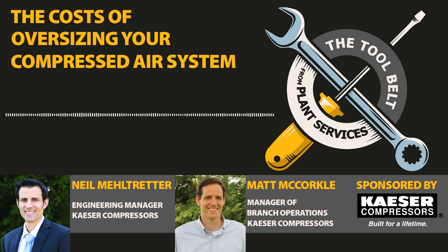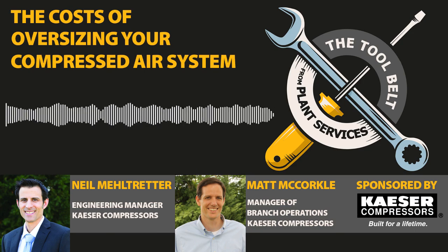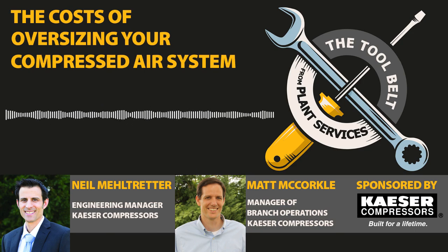And so what that means for customers is they're frequently paying much more for the air they're using than they should be. In fact, we see that the multiple is over a factor of 10. We see customers spending 30 cents per 1,000 cubic feet for their air, and then we see others spending upwards of $3 or more per 1,000 cubic feet. That's really dramatic when you look at the amount of air used in a manufacturing plant. They're using hundreds of millions of cubic feet of air. And if you're paying 30 cents or $3, that's a huge difference in your budget.